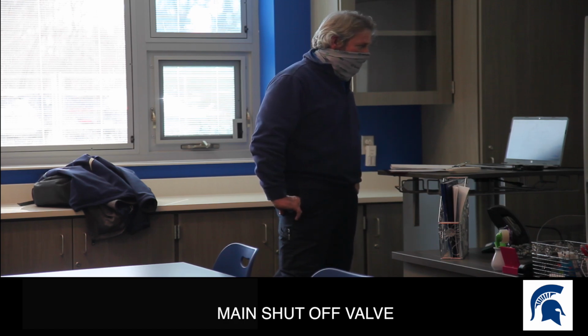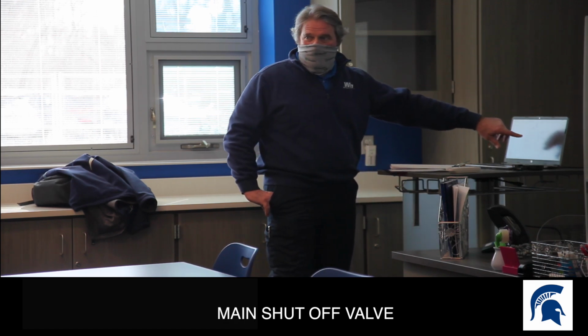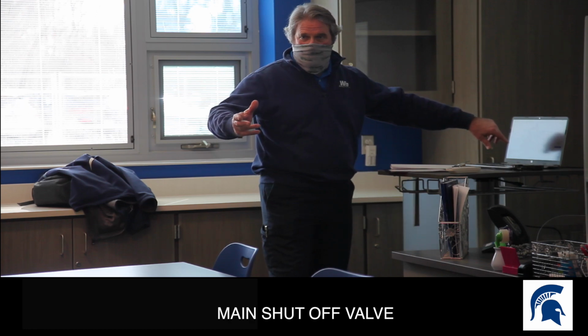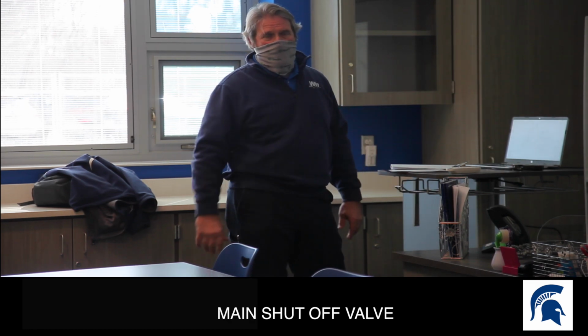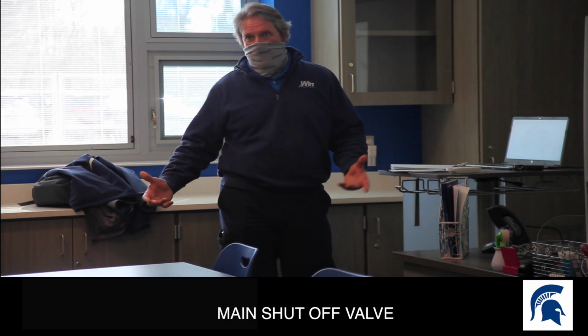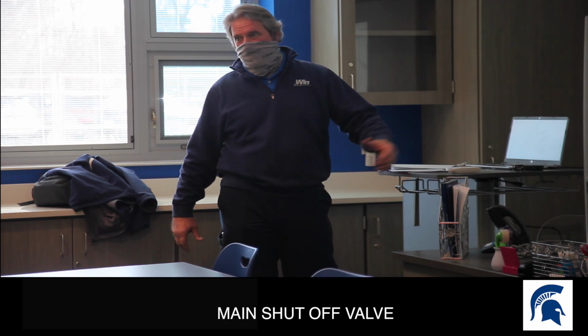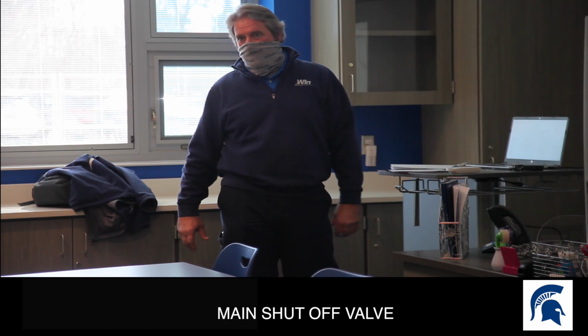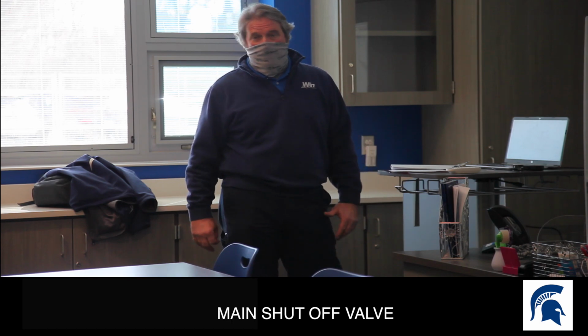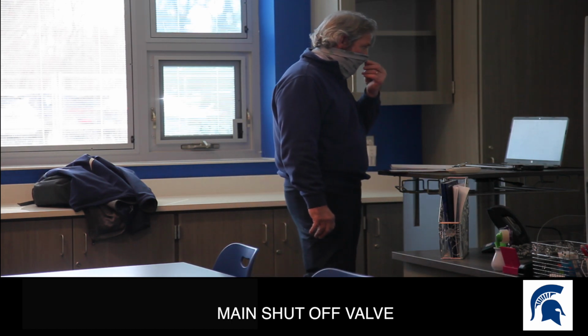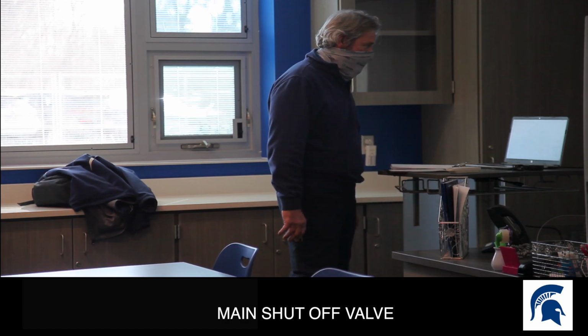And then, like we talked about, there might be a little debris in that strainer. If you have a Y strainer on the system, I do believe you do. So you've got to maintain your Y strainer as well. That helps keep the heat exchanger clear because you're catching your contaminants prior to hopefully entering the unit.